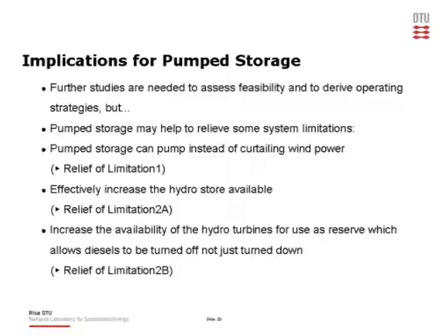It may effectively help to increase the hydro store available, so to increase the amount of water available for the hydro turbines, which is a relief of the first of the hydro limitations. And it may also help to increase the availability of the hydro turbines for use as a reserve, which allows diesels to be turned off rather than just regulated down.